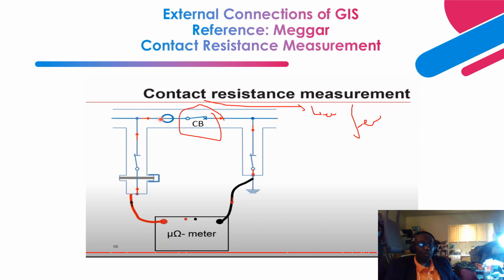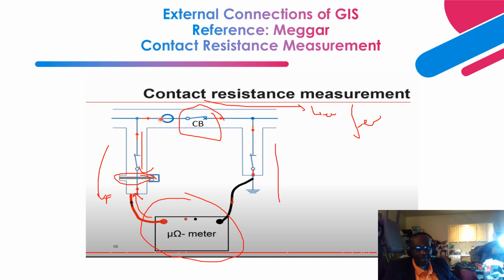So you have your micro ohm meter located here, and you have this one connected here. This disconnect switch is insulated from ground. It is floating, let's call it, and only this side is grounded. Then you have this shorting block, and you have a cap there. So the shorting is in place. It has not been removed.